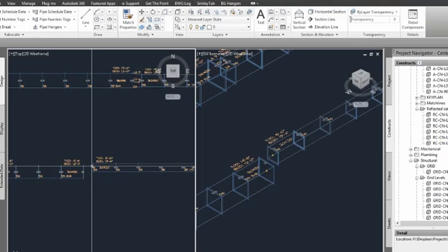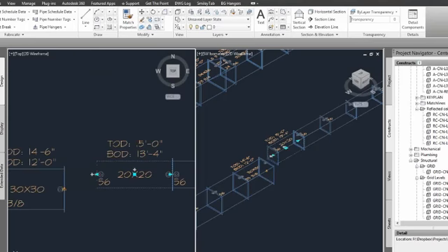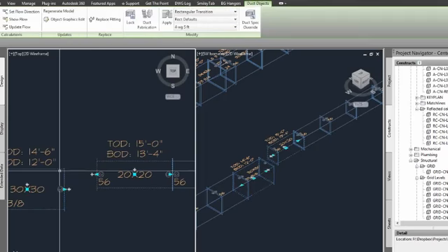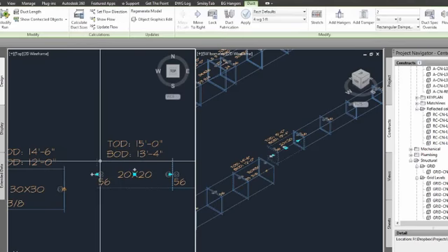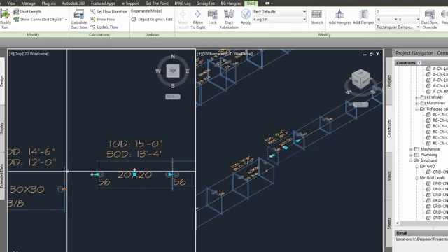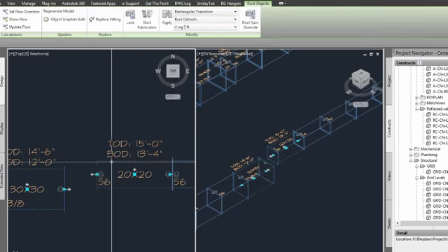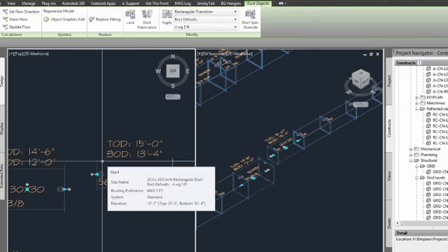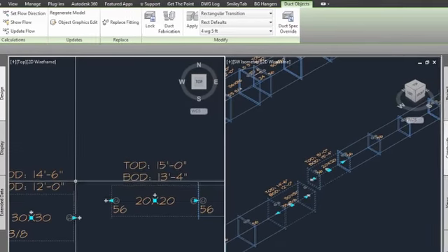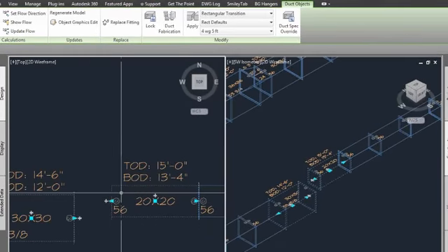We have a tool. If we select both of these pieces of duct, and notice that I'm selecting the smaller duct first and then this larger duct, as if airflow was going from left to right, I am choosing what would be the outlet of the transition first, and then the inlet of the transition. When we select both of those pieces, we get a new tool up here on our duct objects tool tab, and this is what we call our AutoConnect tool.